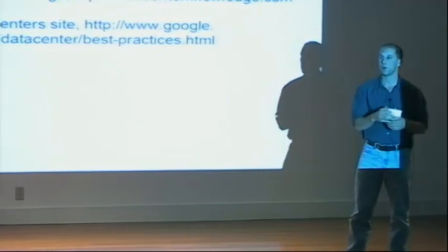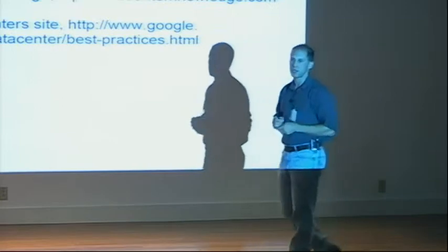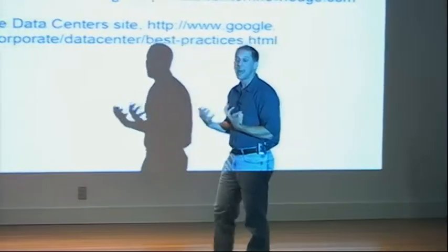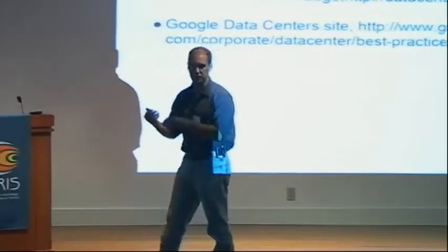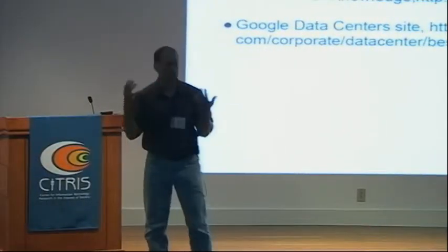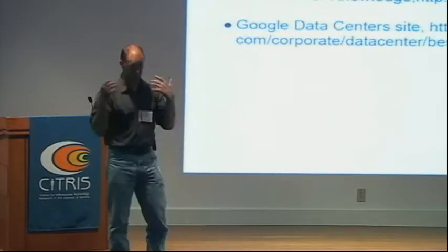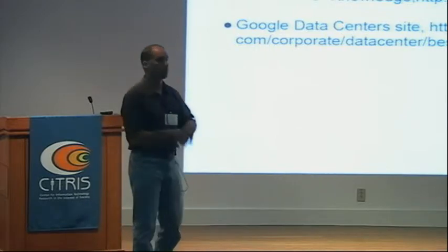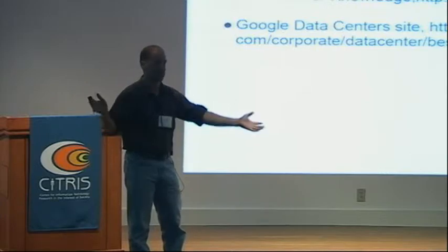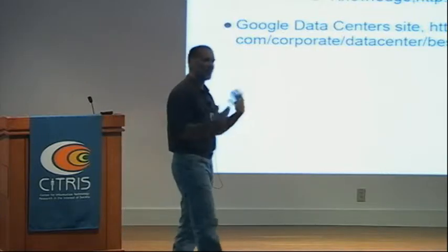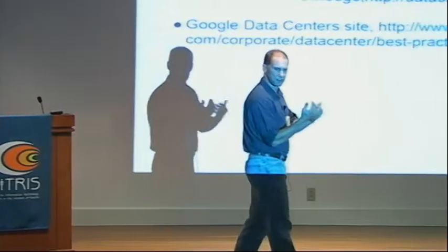As opposed to if we went into a co-location facility, a lot of times they don't have that kind of degrees of freedom. They simply have to say, we will provide you with 62 Fahrenheit air at this many cubic feet per minute, done. And you can't tell them, well, we don't need that. No, that's what you get. That's what our systems are running at because everybody said that that's okay. So that's one of the ways that we get to play with this.